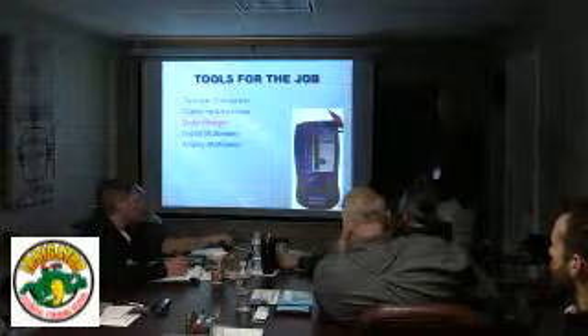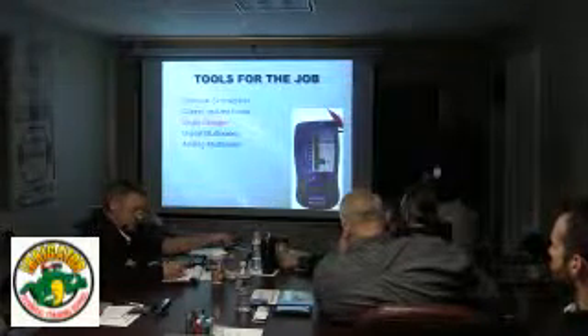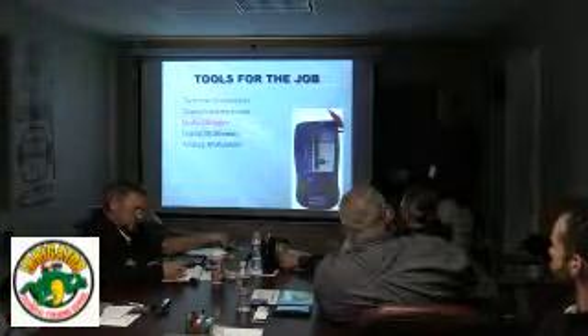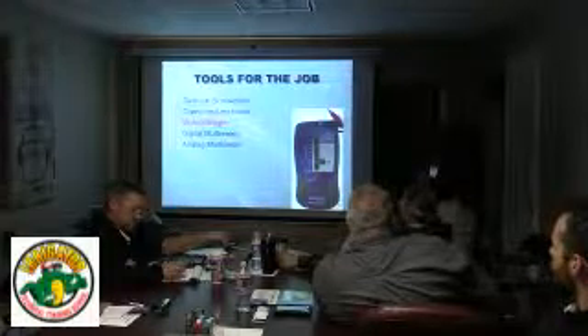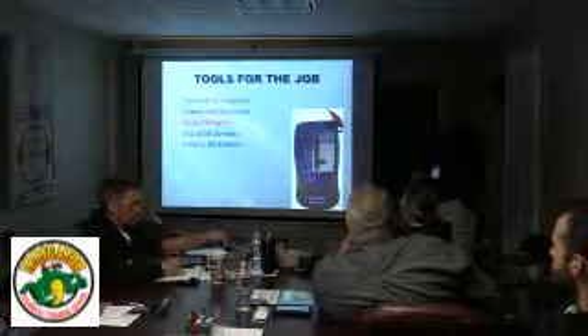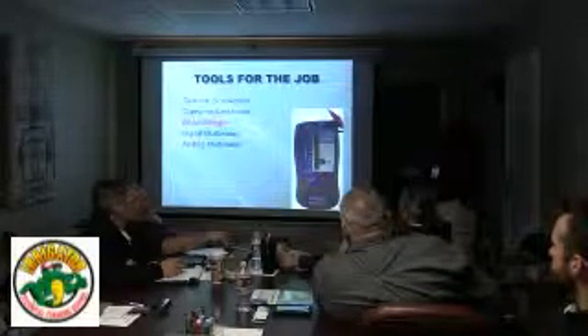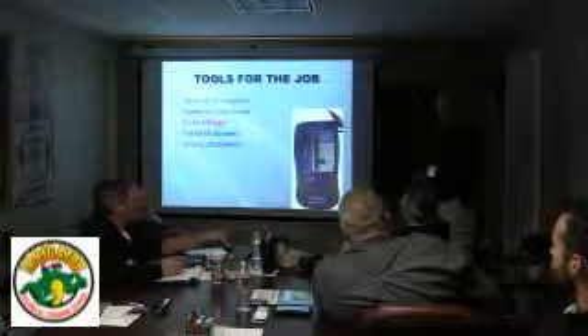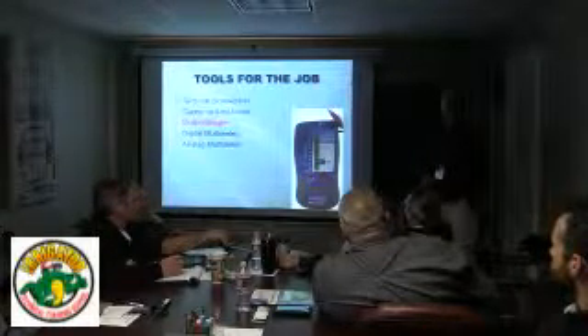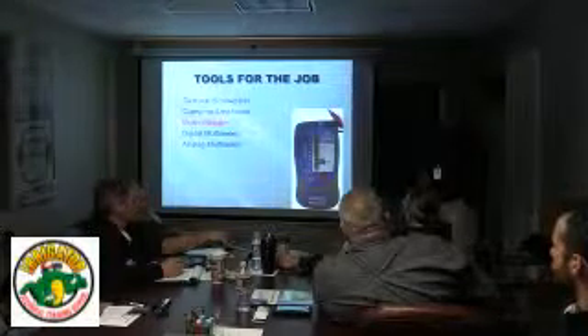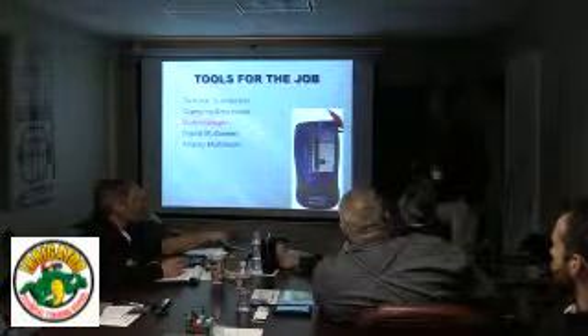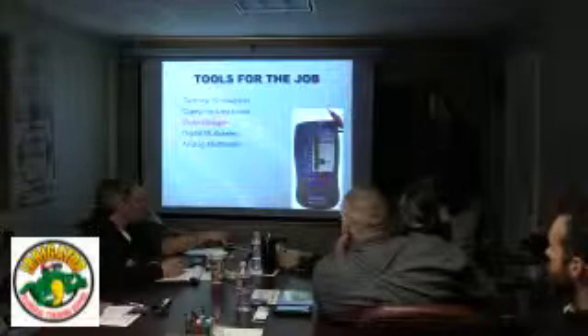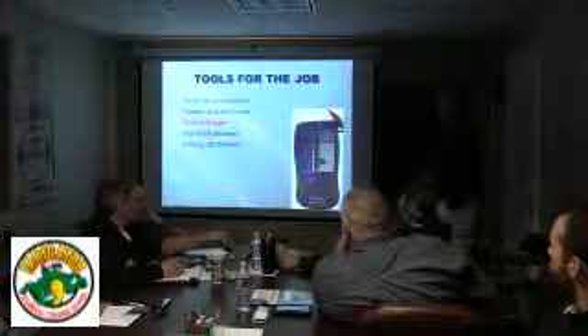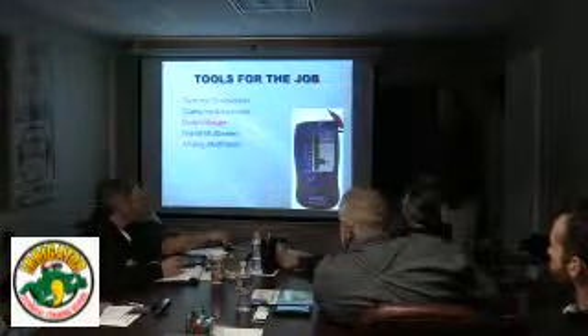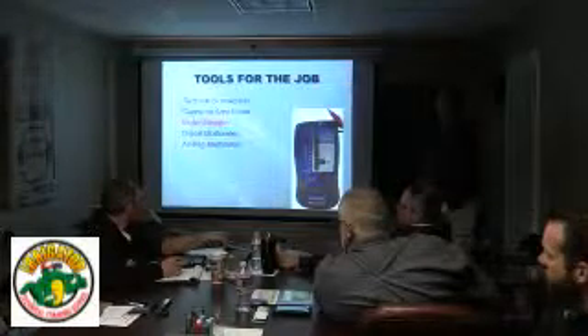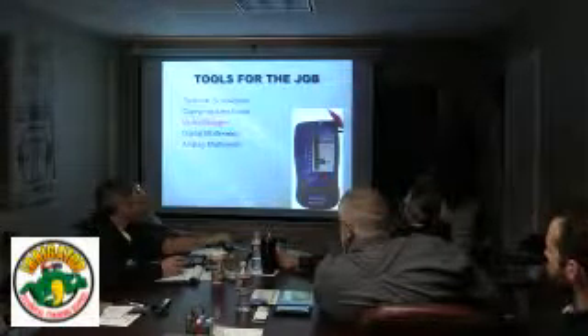I have done a little bit of troubleshooting over the phone where it was either it's a bad motor or it's a bad drive, and we just can't determine exactly what it is, and so they would need to get an electrician that has a motor megger and come back and double check before they pull a pump out of a well that's 100 foot deep or something. These won't work on a submersible. They don't work very good on a submersible, no they don't. They won't. You gotta have the hand crank to it. Especially with long motor leads.